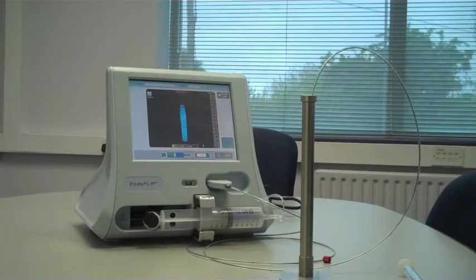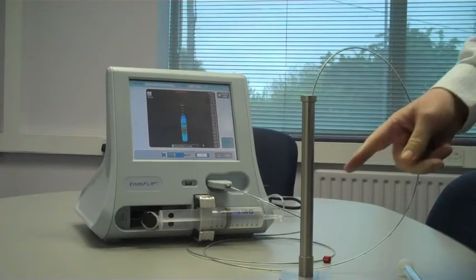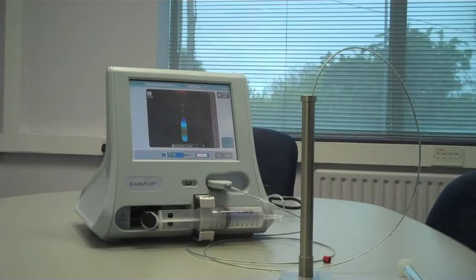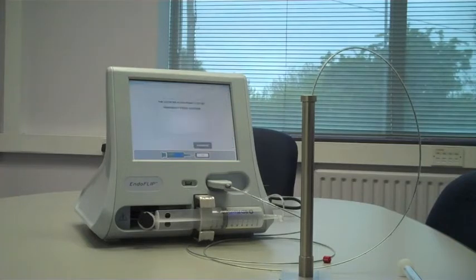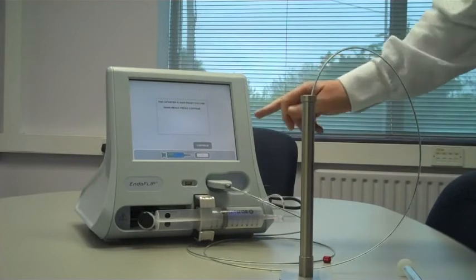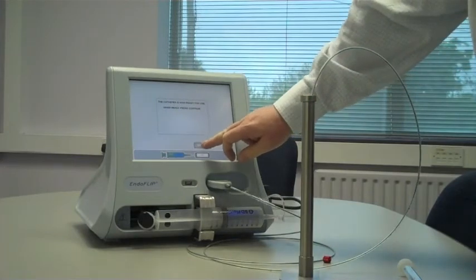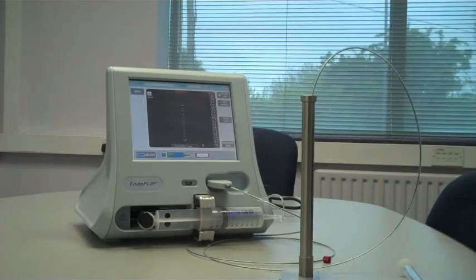Straight after this, the system is going to zero the pressure transducer that sits within the balloon itself. There's one solid state pressure transducer, and that's used for measuring how much you are inflating the balloon by, what sort of pressure you're inflating the balloon by. So it says the catheter is now ready for use. Hit continue, and essentially you're all good to go.